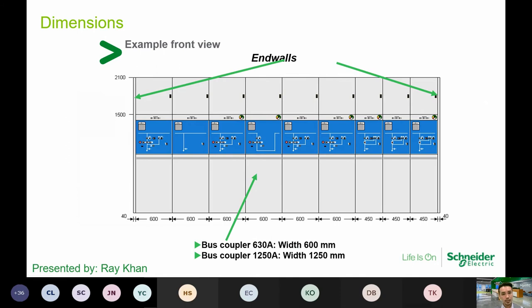So over in here, this slide shows how small the footprint of the GMA is. As an example, a front view of the model of a GMA, for a 630 amp, the width is only 600 mm, right? Of course, we also have to factor in the end walls. The end walls are 40 mm on both ends. So adding both sides, it will be 80 mm, all right? For the bus coupler compartments, once it goes up to higher, like 1,250 amps, the width will be much wider as well, 1,250.